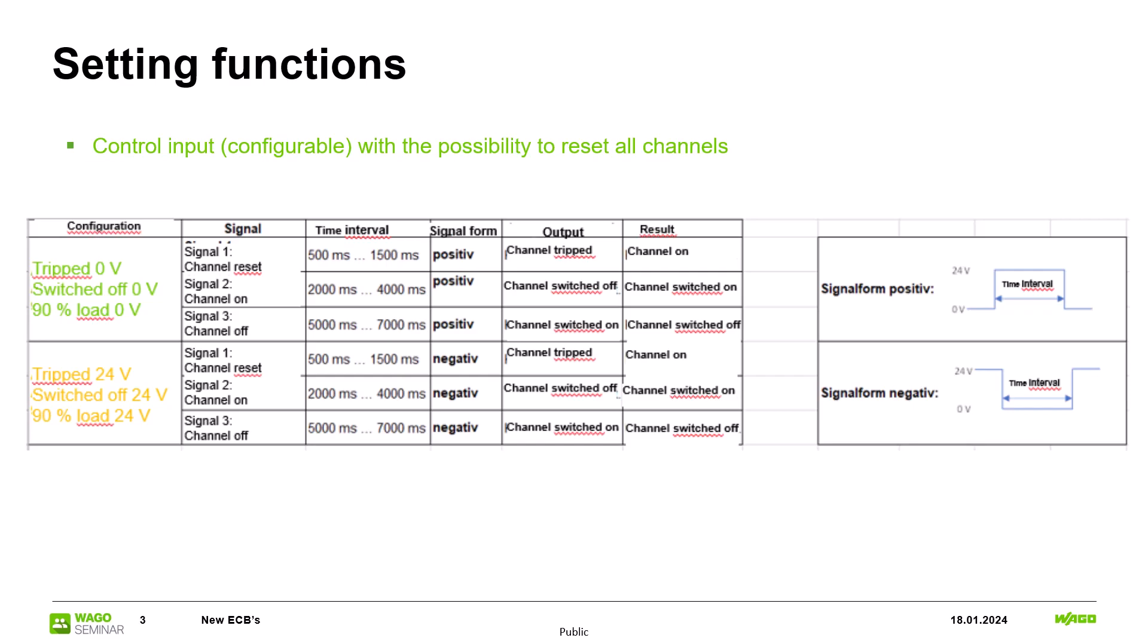If the input signal is between 500ms and 1500ms all channels will reset. Between 2000 and 4000ms all channels are switched on and between 5000 and 7000ms all channels are switched off. These circuit breakers cannot be used to switch individual channels on or off.